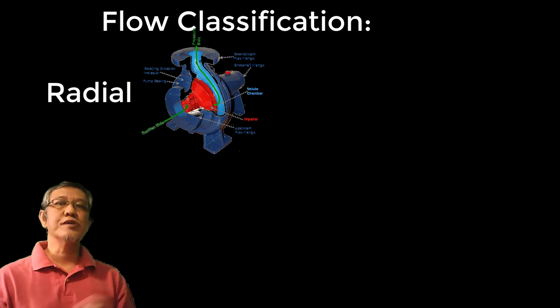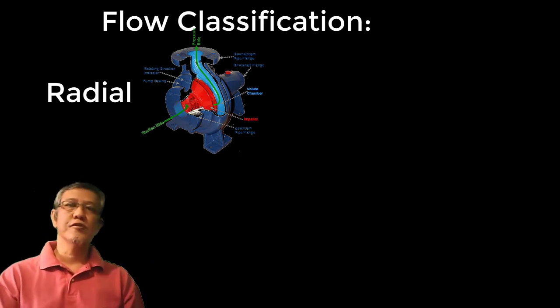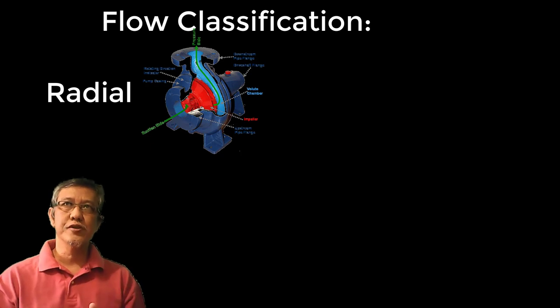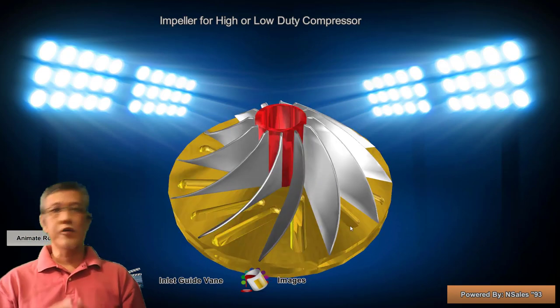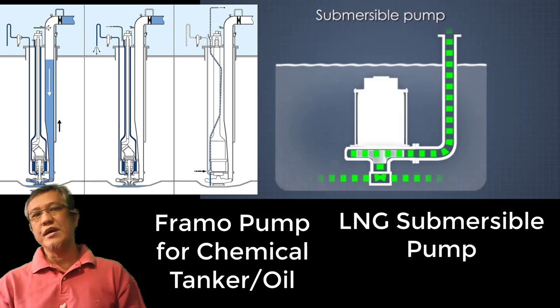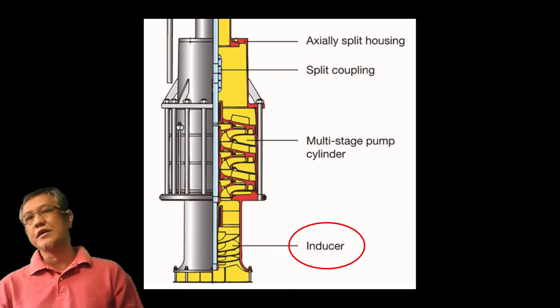The first one, which is radial, is a very common type which can be seen on board ships, such as booster pumps and pumps you can find on oil tankers with a pump room, and also on common gas tankers or chemical tankers. We can also see a combination of radial and axial, or mixed flow types, such as for the LNG high and low duty compressors — they use the so-called radial and at the same time axial, so they call it mixed flow. For the submersible LNG pump, it is called axial type, and also radial type, wherein in a mixed flow they put in a so-called inducer before the impeller, which is what makes it a mixed flow.